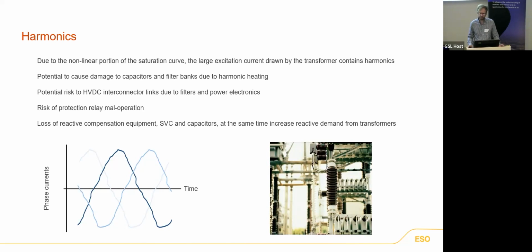And the risks can be combined. So you could have a loss of reactive compensation equipment like that SVC I showed in the picture on the last slide, which is there to balance the reactive power, make sure we've got the right voltage levels. You might lose that due to protection malfunction, but then you also have an increase in reactive power absorption from your transformers at the same time. And that's actually what they think happened in Quebec in 1989. So they were seeing voltage drops at the same time they lost reactive equipment.